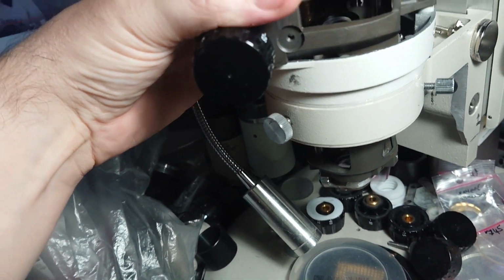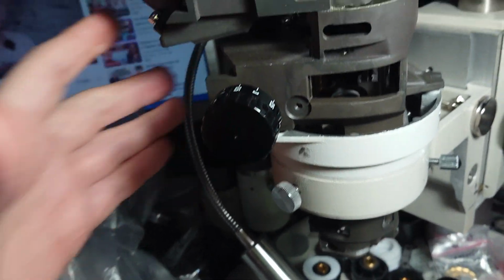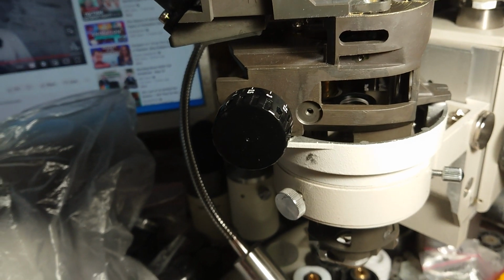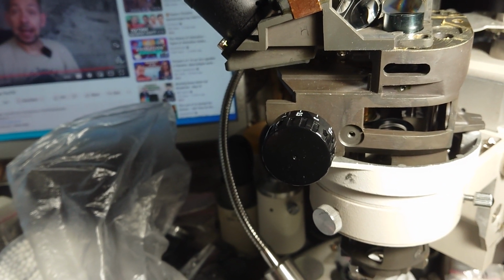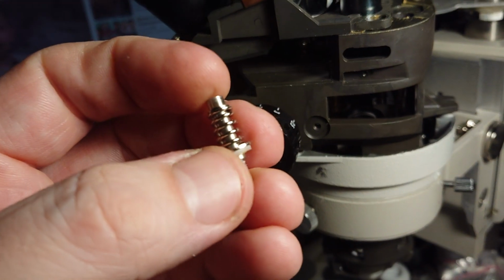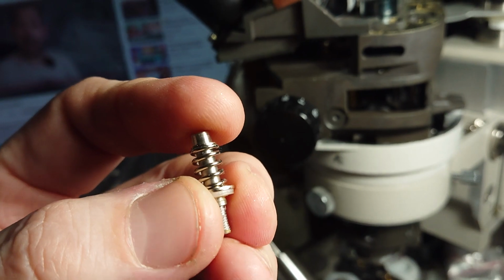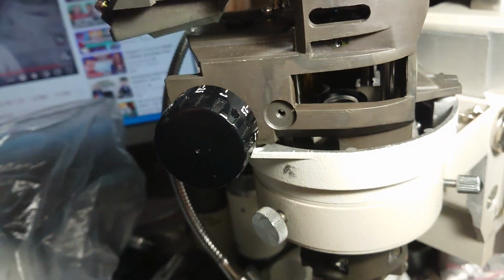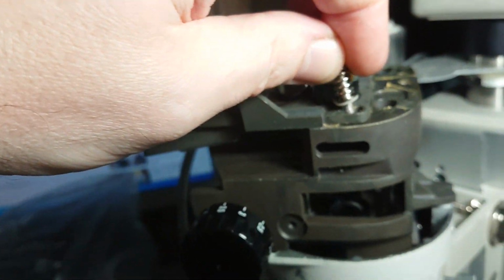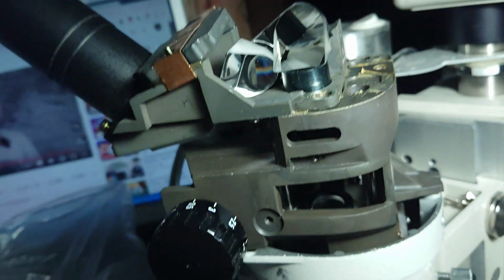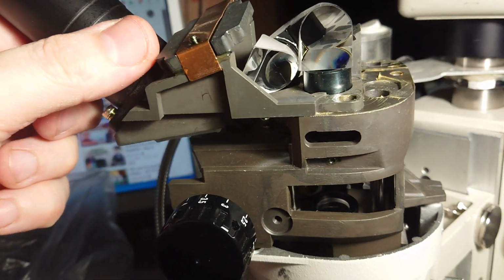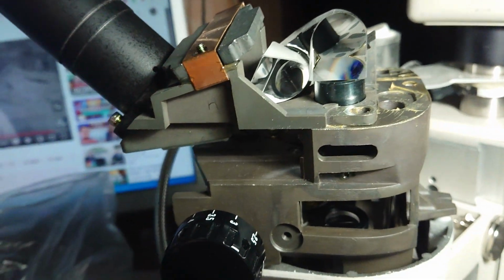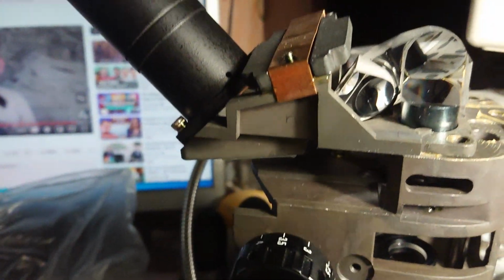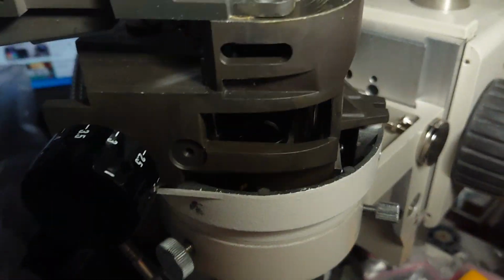And by the way, I need to say that the inclination eyepiece tube and erecting system are connected with such, how to say, a bolt and little springs here, so all this system works this way. This bolt is screwed into the case, and those little springs are pushing, assembling two parts of the microscope and the inclination erecting system. So not that bad a thing in design.